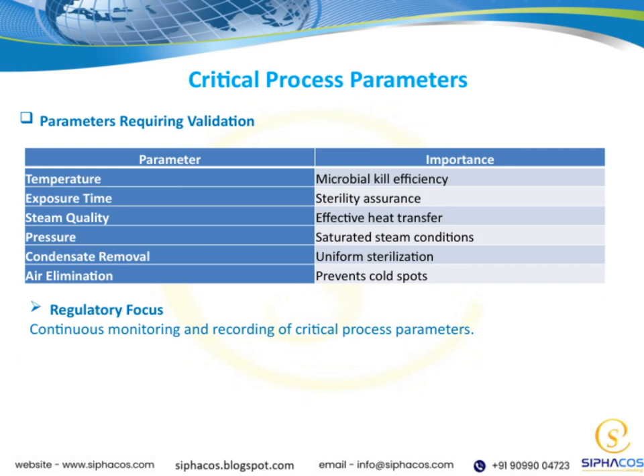Steam quality matters too. It affects heat transfer. Pressure helps maintain saturated steam conditions, while condensate removal and air elimination prevent cold spots and ensure uniform sterilization. Each parameter requires careful validation to meet strict standards and keep processes reliable.